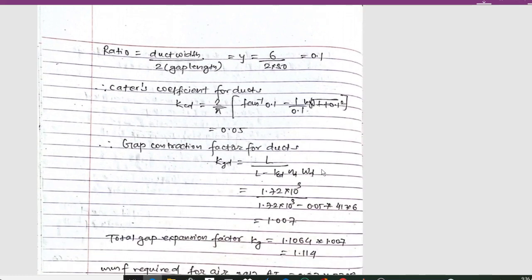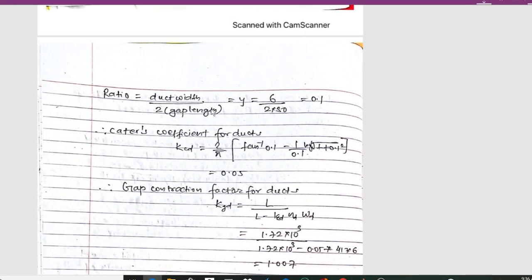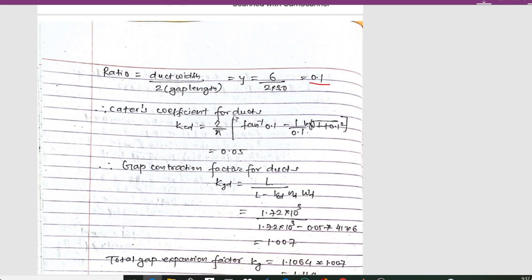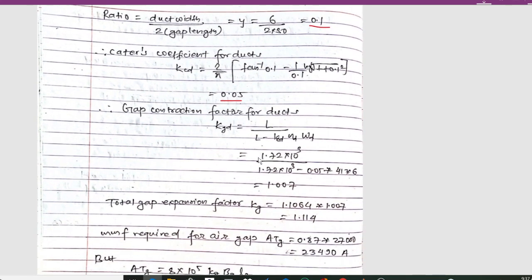For the duct, y = wd / (2 × lg) = 6 / (2 × 30) ≈ 0.1. The Carter's coefficient for the duct, Kcd = (2/π) × [tan⁻¹(y) − (1/y) × log√(1 + y²)], substituting y = 0.1 gives Kcd = 0.05.